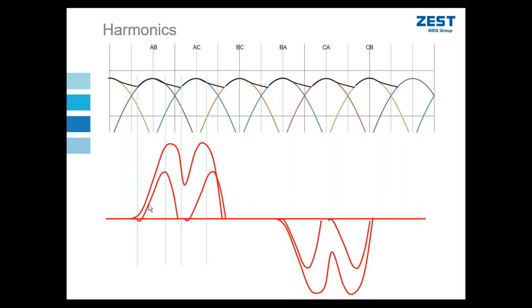Let me compare that to the low load condition. My current amplitude has increased, obviously, because I'm saying that my load on my motor has increased. But in addition to that, the actual waveform shape drawn from the supply has improved. My distortion is lower, is less.